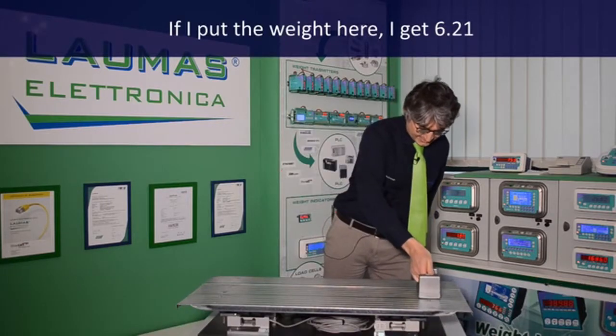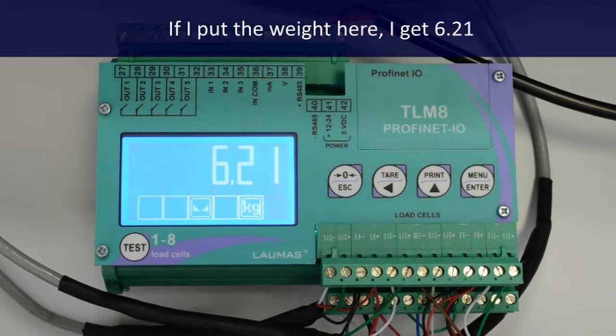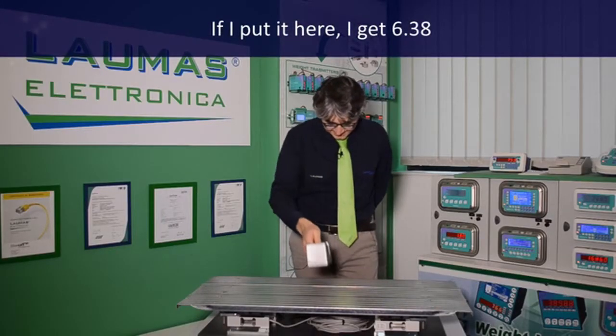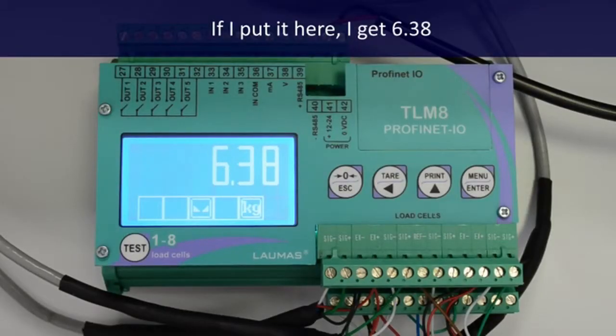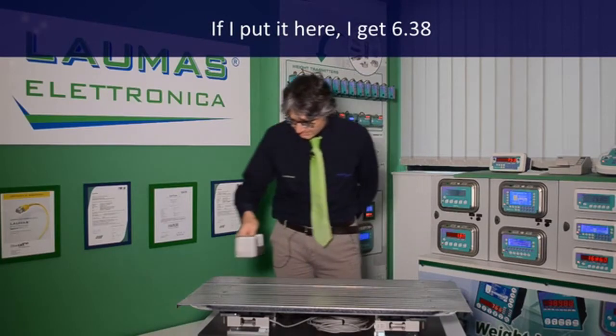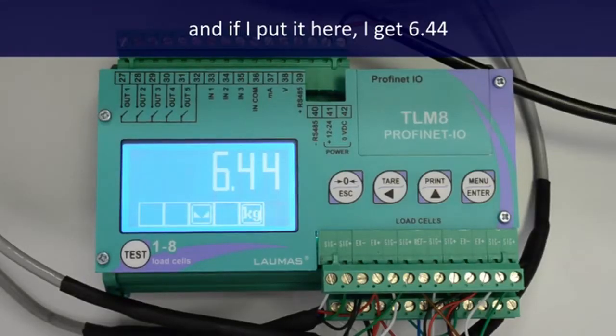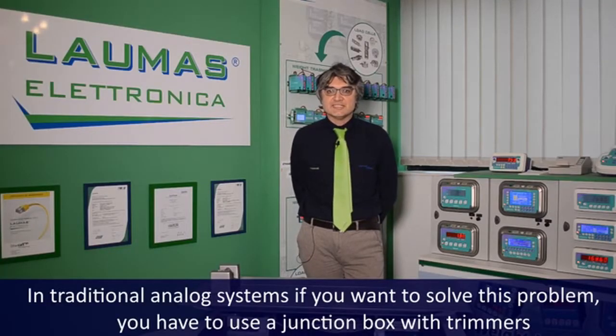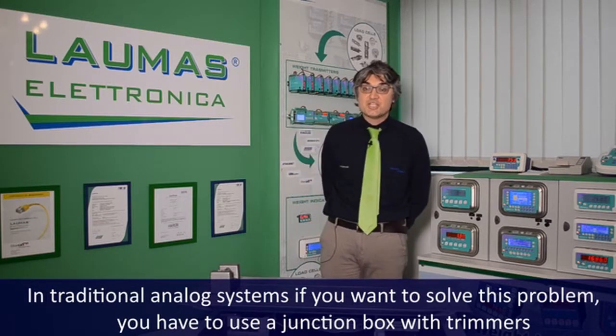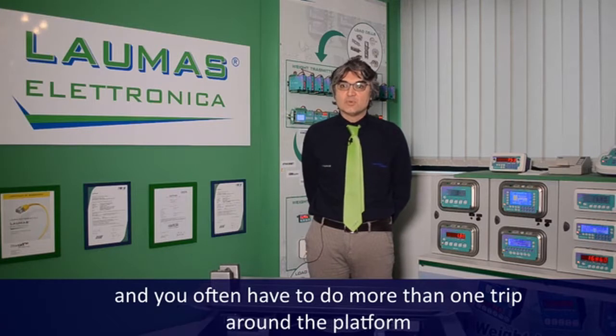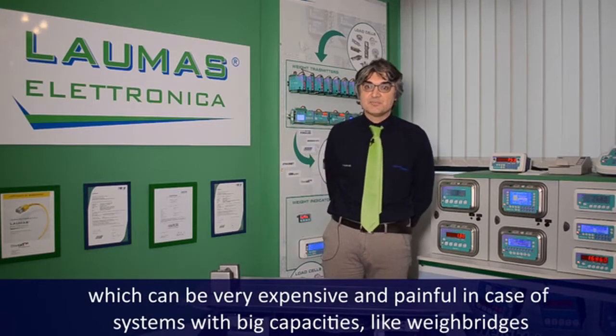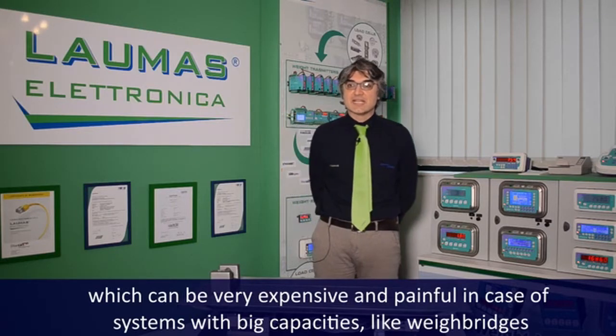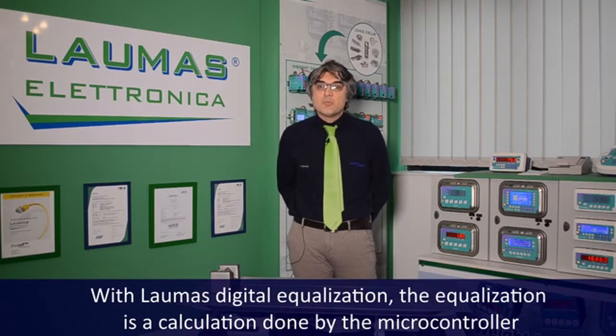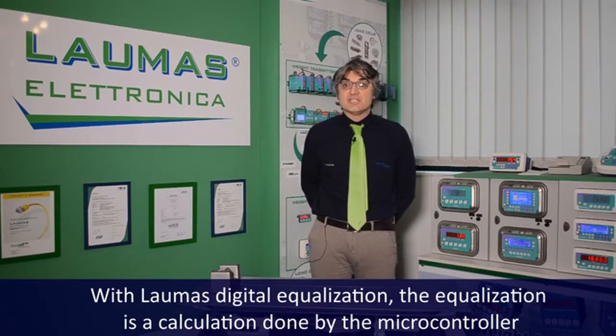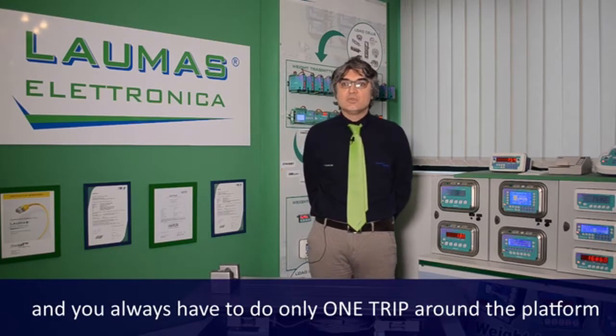If I put the weight here, I get 6.21. If I put it here, I get 6.38. And if I put it here, I get 6.44. In traditional analog system, if you want to solve this problem, you have to use a junction box with trimmers, and you often have to do more than one trip around the platform, which can be very expensive and painful in case of a system with big capacities like weighbridges. With LAUMAS digital equalization, the equalization is a calculation done by the microcontroller, and you always have to do only one trip around the platform.